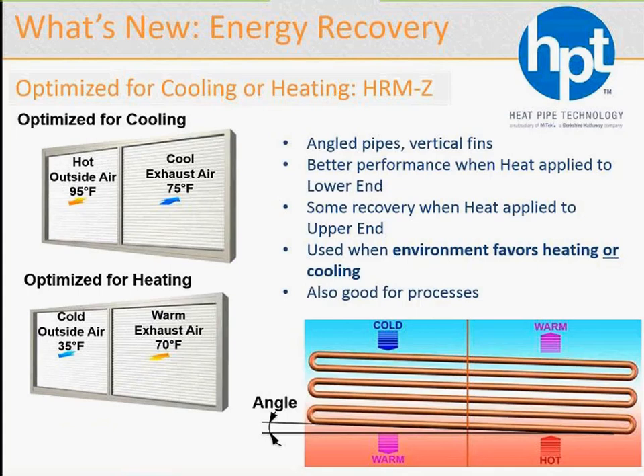The one optimized for heating, as you can see on the left, is cold outside air of 35 degrees, which happens to be the higher end, and the warm end is the lower end, at 70 degrees. The golden rule of thermosiphon heat pipes is the warm air is always on the lower end. Of course, it can work when it's level, but enhancements can take place, and as we show you the performance, you will see that it does actually make a difference if you have a little angle.